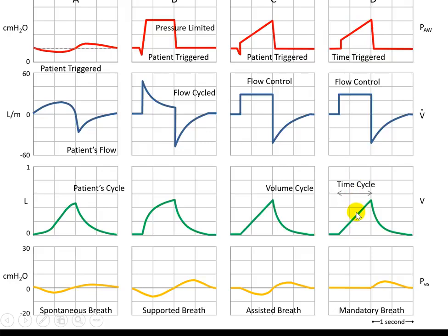The same breath that is started by time delivers the control — the set tidal volume — with a square wave flow. If this breath is instead started by the patient, and the machine delivers the same control volume, we call it an assisted breath. The only difference between an assisted breath and a mandatory breath is the trigger: here it is time triggered, and here it is patient triggered — either flow or pressure. Both mandatory and assisted breaths could be either volume cycled or time cycled.